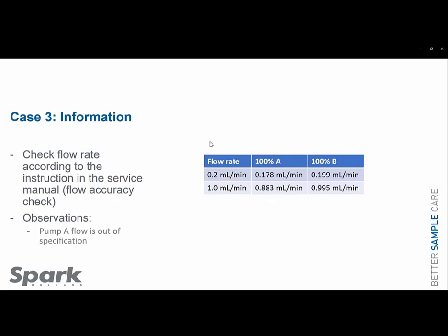We will check the flow rate according to the instruction in the service manual, flow accuracy check. We will do that for pump A as well as pump B at a flow rate of 200 microliters per minute and 1 ml. We observe that pump B is doing fine. The result of this flow rate check is good, within specifications. On pump A, we have a deviation. It should be better than plus minus 10 microliters. So pump A is suspected to be the source of the problem.